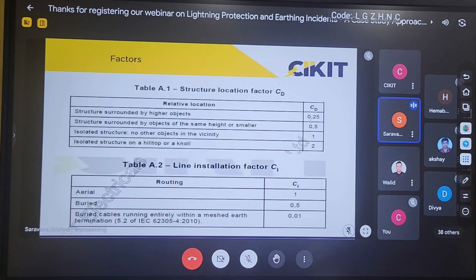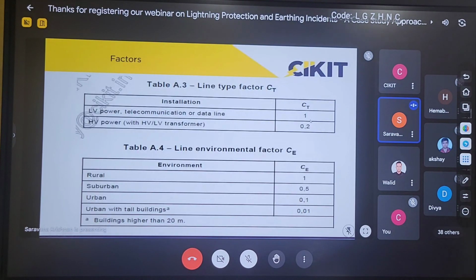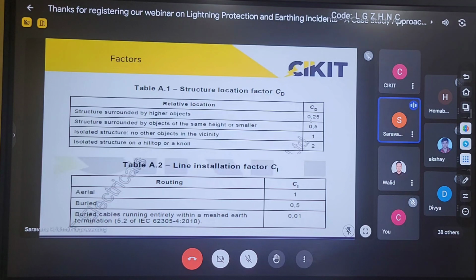If my building and the other buildings are of the same height, then the risk will be moderate, so the value of CD is 0.5. If my building is located in an isolated area, then the value of CD will be 1. And if my building is located on a hilltop, the risk will be much higher, so CD is denoted as 2. From this, we can observe that the value depends upon the surrounding environment as well, whether my building is surrounded by taller structures or my building is the taller structure. That is one of the important parameters.